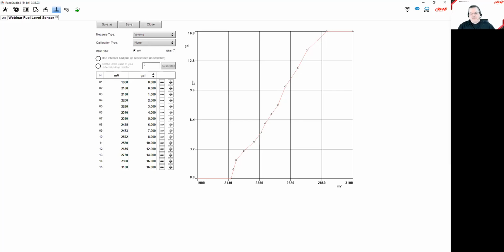The other trick I like to do, though it's not needed, is down at the bottom—in this particular case, 2160 millivolts equaled 0 gallons. When the sensor was at 0 gallons of fuel, it read 2160 millivolts.